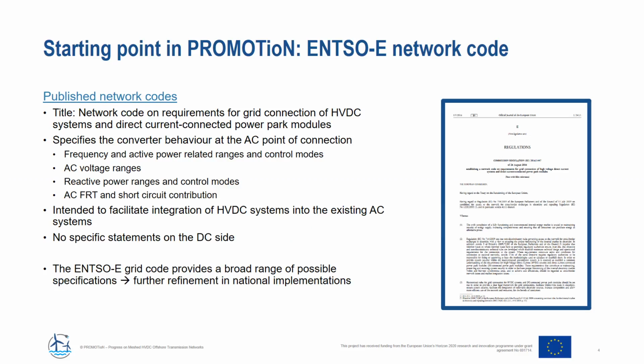The starting point in this work was the ENTSO-E network code, which is published as a Commission regulation with the official title Network Code on Requirements for Grid Connection of HVDC Systems and Direct Current Connected Power Park Modules. So the title already alludes to the fact that this grid code specifies the converter behavior at the AC point of connection, including frequency and active power related ranges and control modes, AC voltage ranges, reactive power ranges and corresponding control modes, AC fault ride through and short circuit contribution.